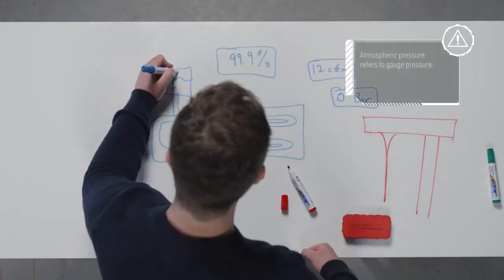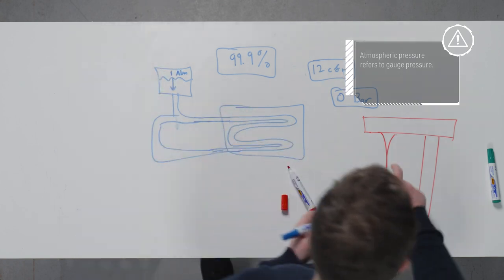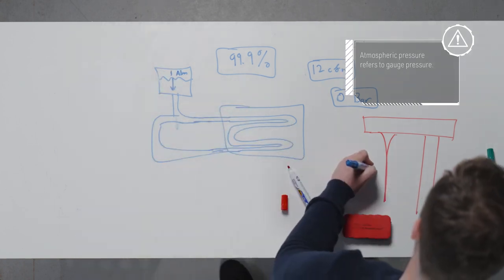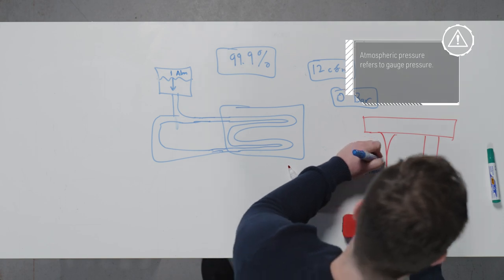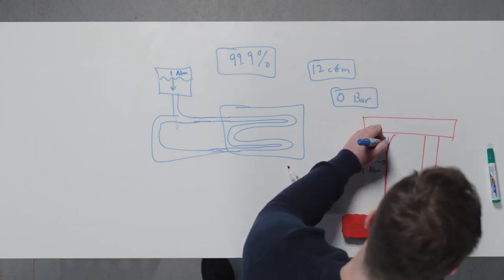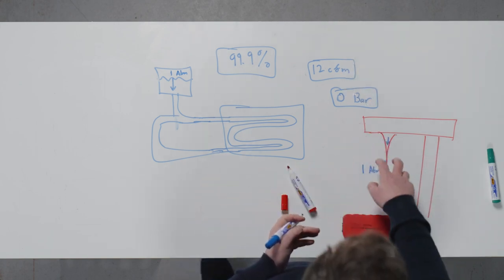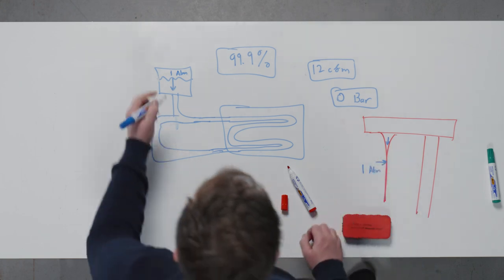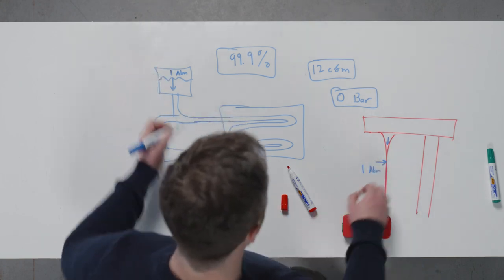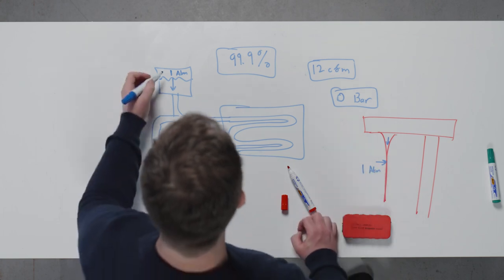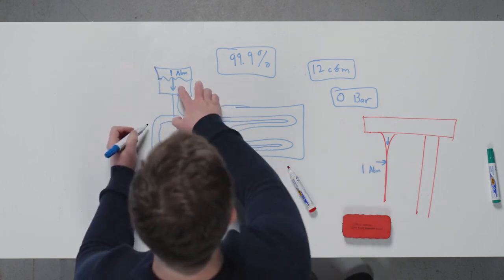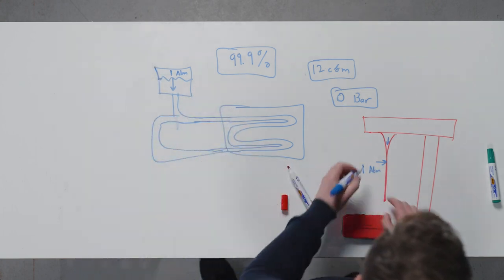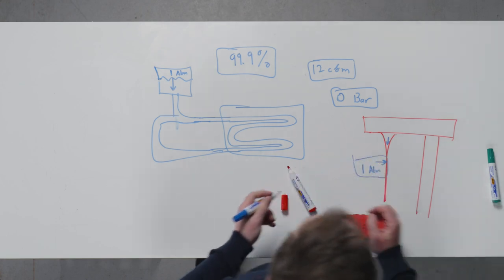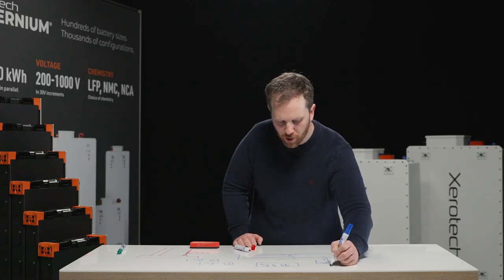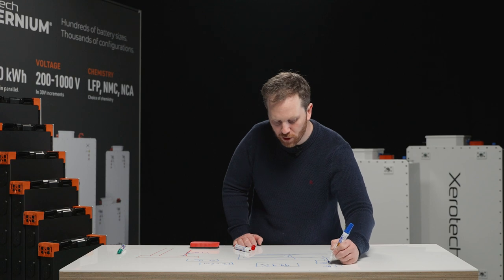You'll have ambient air pressure up here, which is basically 1 atmosphere, and then you'll have ambient air pressure out here of 1 atmosphere. So the force going this way and the force going this way is the exact same. It will not open the duct. So instead, during the fill procedure, you need to force the coolant in. So the pressure that you're pushing the coolant in at must be greater than this air pressure. It doesn't have to be much. It can be 1.1 bar, 1.2 bar.